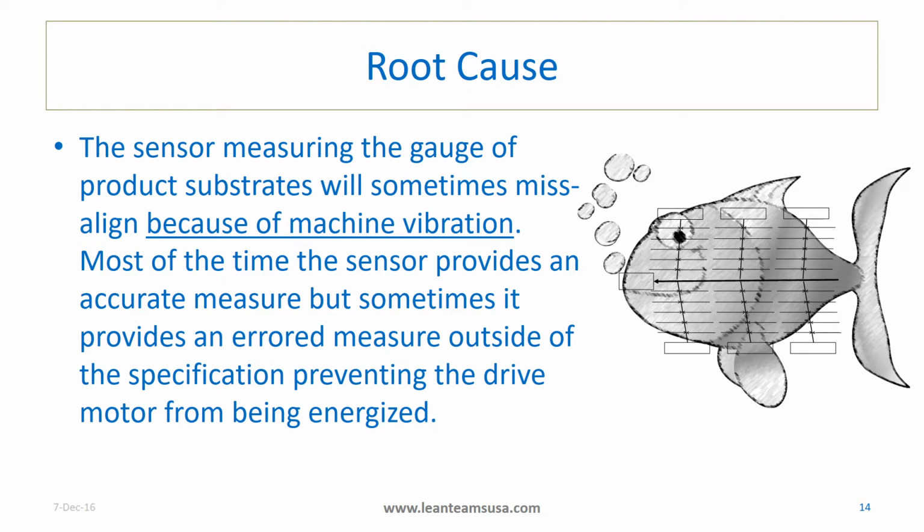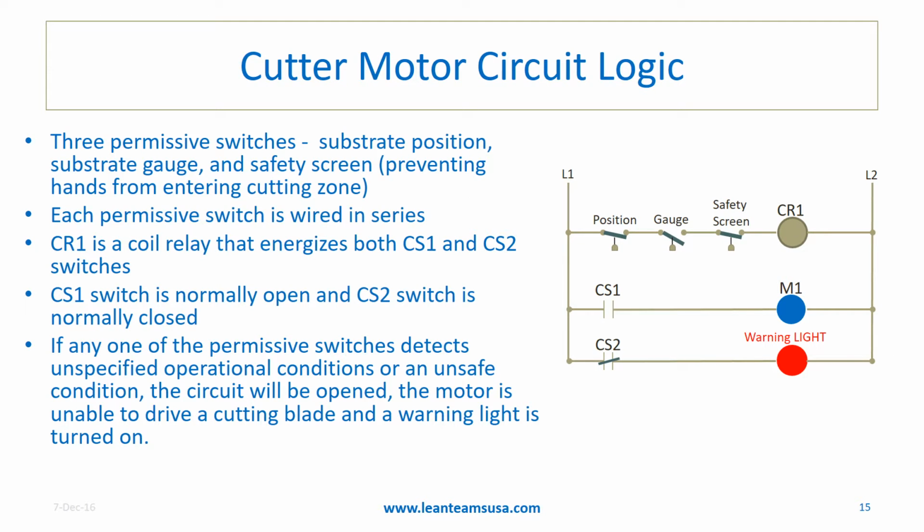There was no root cause determined in either maintenance request. The root cause was not complex. The sensor would sometimes move because of vibration, and with some problem solving applied, this fault could have been easily eliminated. Let's look at the value of the two tools the maintenance team decided to invest in 2 years ago.